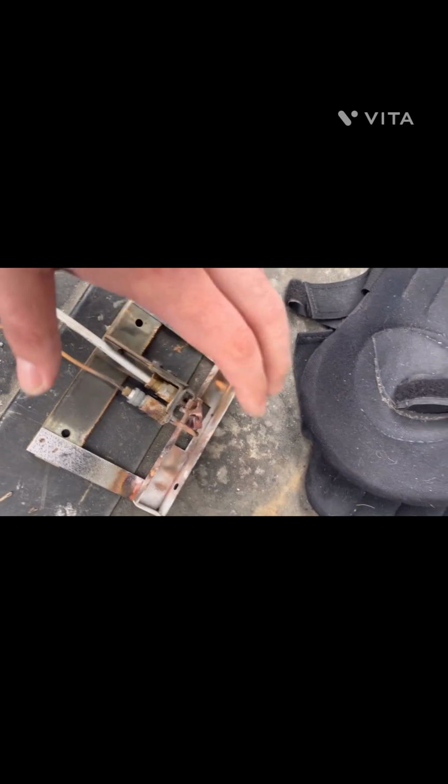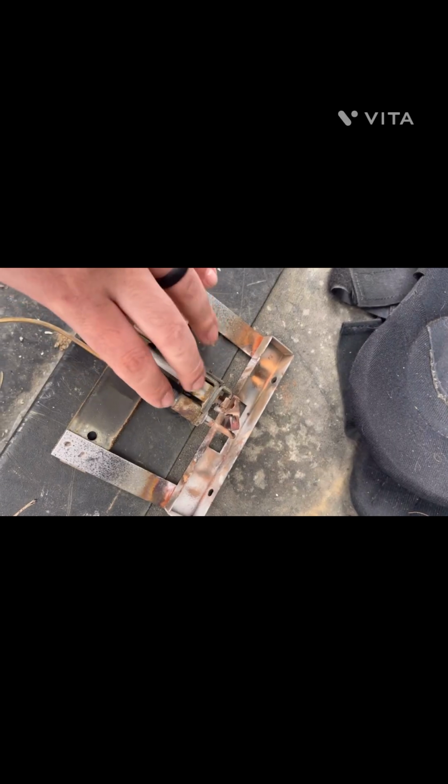What we're gonna try to do is, I'm thinking that this is bad. There's possibly blockage inside this valve here. There's a lot of soot buildup on here anyway, but it also might be the igniter as well. We're gonna take this apart, double check the valve, make sure everything is good over there. If it's not, the valve may have just died. It was a year ago that these people took a look at this assembly and this setup, so it's very possible that we may have to try to replace this. If we can't get the parts, then we have to replace the furnace.